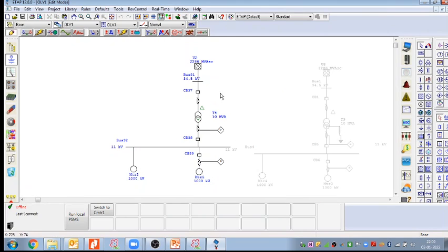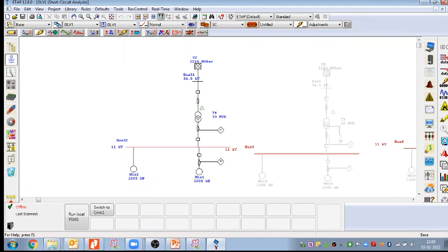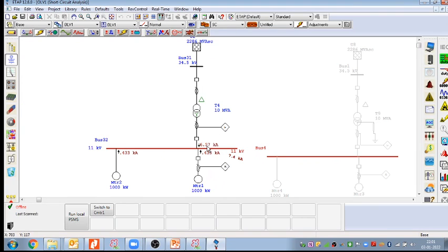Here the system is ungrounded. Now this is my short circuit analysis. This tab is for this. If I take this tab, here is the result, showing what kind of current we want to simulate. Let me take Run Three Phase Device Duty. If I run this, what will happen? Let us see. With the three-phase fault current and the system ungrounded, the value is coming to 6.57 kiloamperes, right? Now let me take another example. Let me take the 60909. Let me go with the L2G fault. Now let me change the type of the fault.